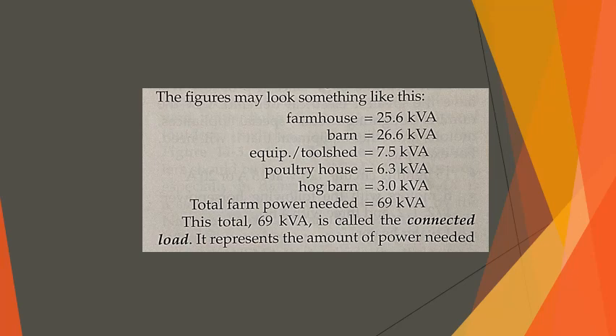Again, a more conservative figure is the demand load, which represents the amount of power that would probably be needed at any given time. Generally, the minimum demand load is considered to be about 35% of the connected load. Based on this figure, the wire sizes and overcurrent protection at the yard pole are determined.